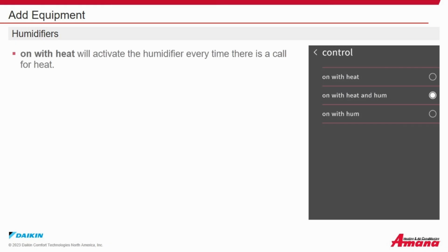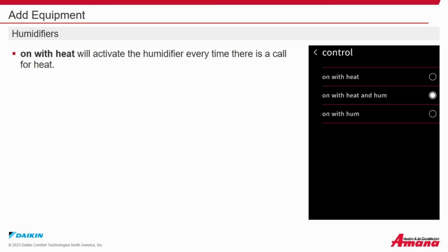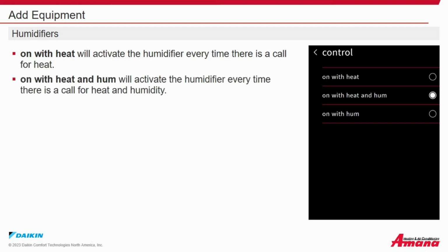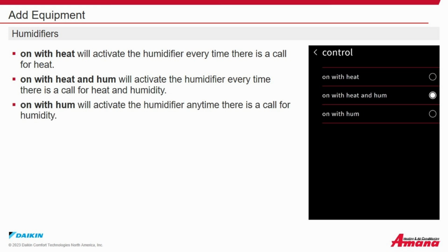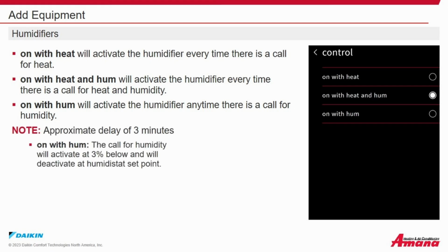Humidifiers. If the control is set to on with heat, it will activate the humidifier every time there is a call for heat. If the control is set to on with heat and humidity, it will activate the humidifier every time there is a call for heat and humidity. If the control is set to on with humidity, it will activate the humidifier anytime there is a call for humidity. Note: approximate delay of 3 minutes. On the setting of call with humidity, the call for humidity will activate at 3% below the humidity set point and will deactivate at humidity set point.